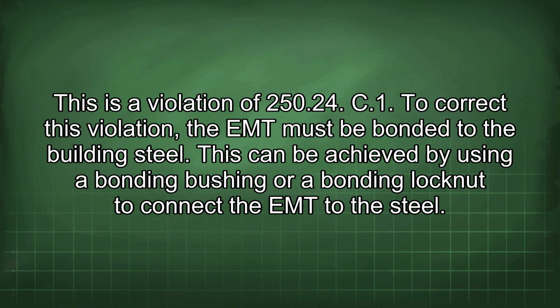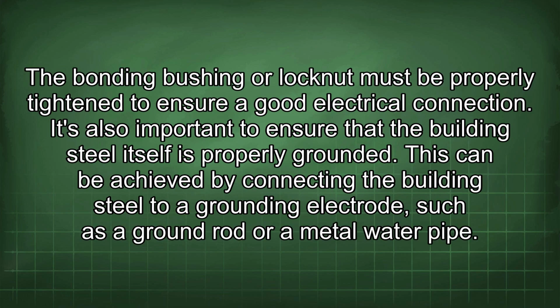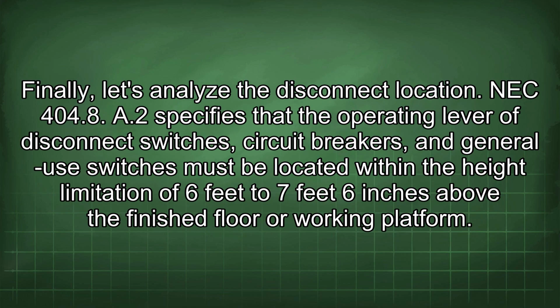This can be achieved by using a bonding bushing or a bonding lock nut to connect the EMT to the steel. The bonding bushing or lock nut must be properly tightened to ensure a good electrical connection. It's also important to ensure that the building steel itself is properly grounded. This can be achieved by connecting the building steel to a grounding electrode, such as a ground rod or a metal water pipe. Finally, let's analyze the disconnect location.